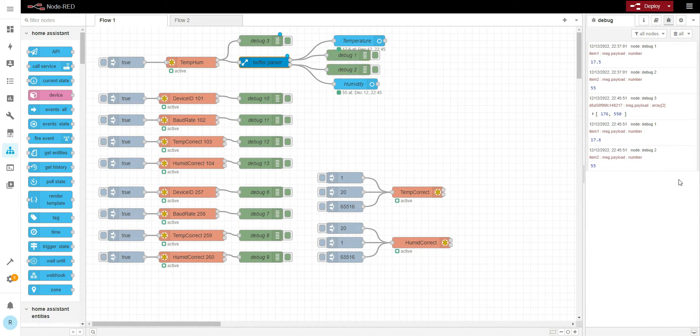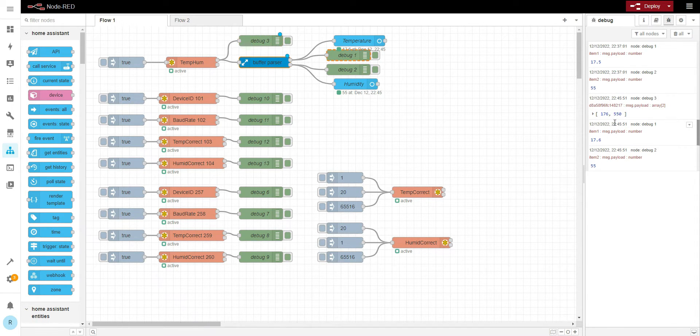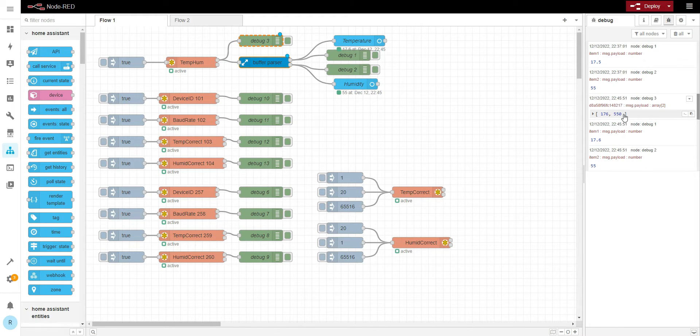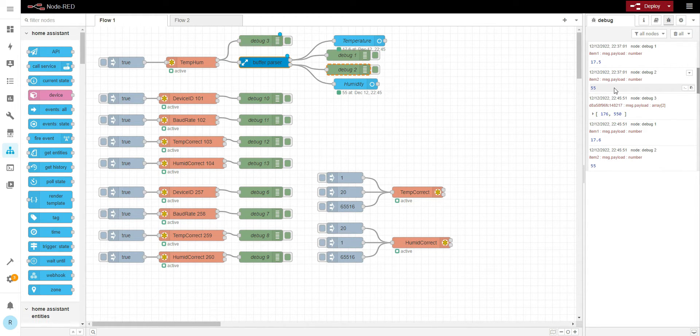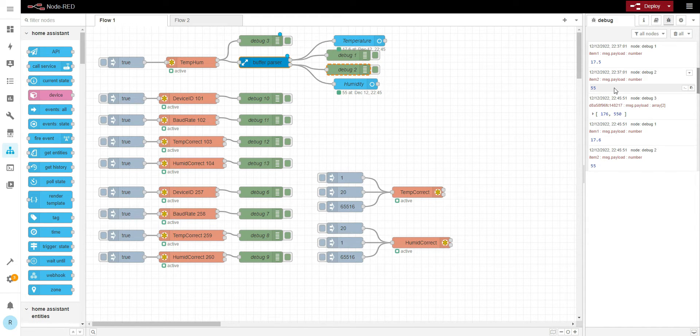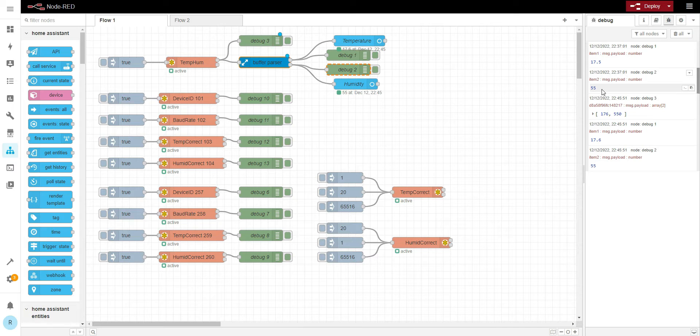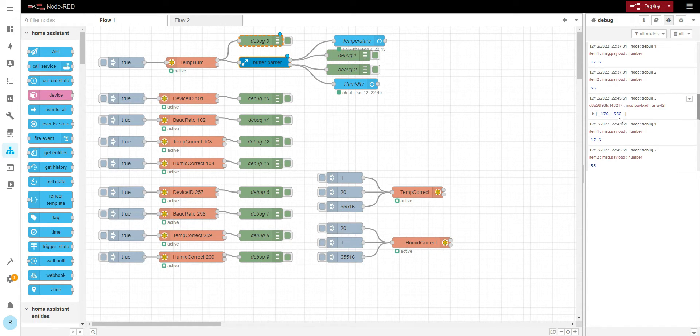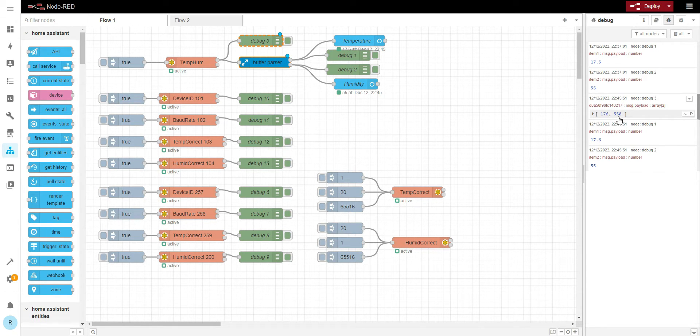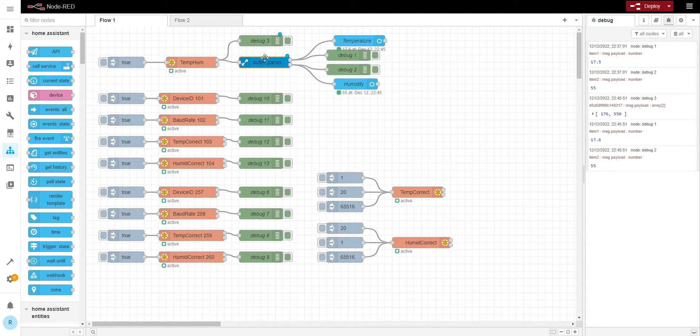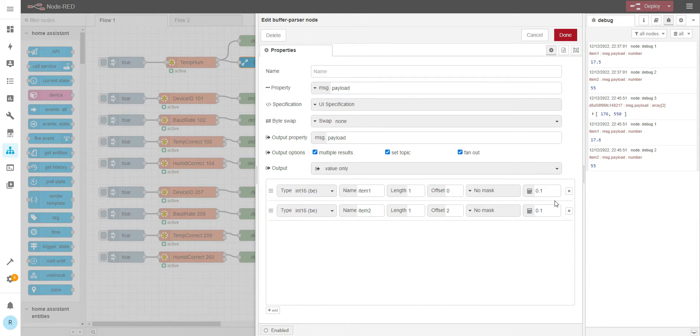If we read directly, we got 176 and 550. Basically, if we read an integer value, it won't have the decimal space. So the common thing they do is multiply first, and then when we read it we need to divide it by 10, or sometimes by 100. So if it's 550, that means it's 55%. Or if it's 176, that means it's 17.6 degrees. So this multiplier does the job.